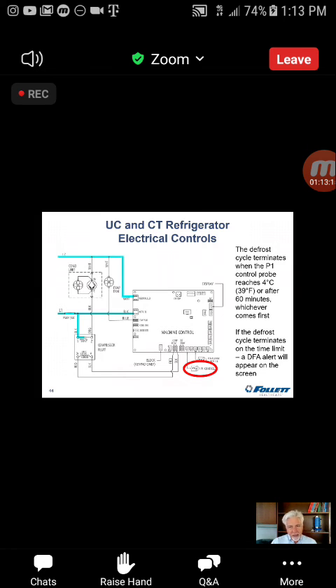Now on refrigerators, that normally doesn't have big complications. It normally means that we have product shoved up against there. We're not getting adequate airflow through there. It's usually not an indication that there's anything wrong with the equipment. Now, freezer is a different story. All right, but on refrigerators, just look for some obvious stuff like they've got product packed up against that, because that will affect the termination of the defrost cycle.